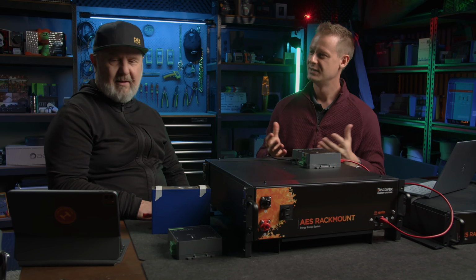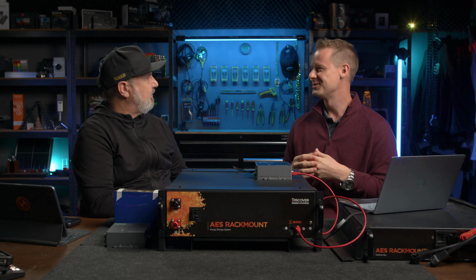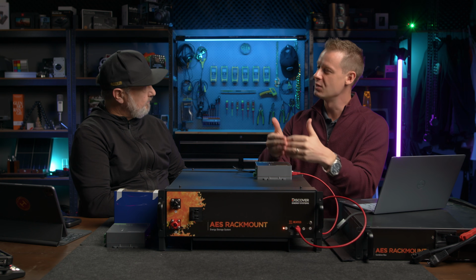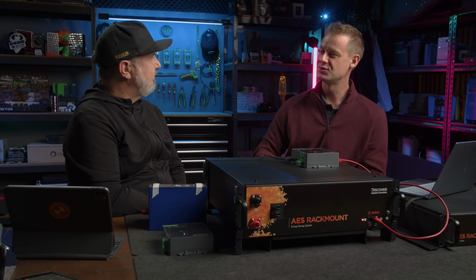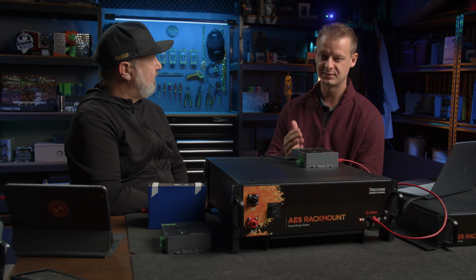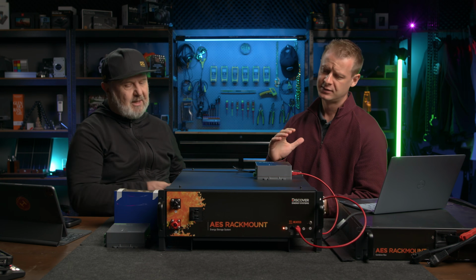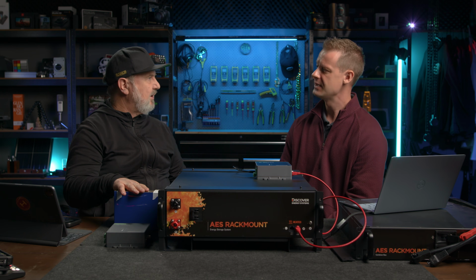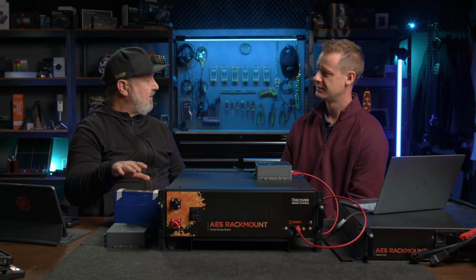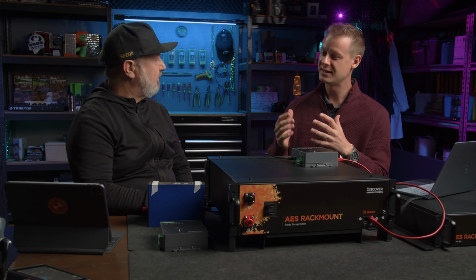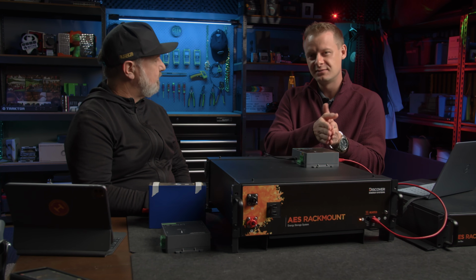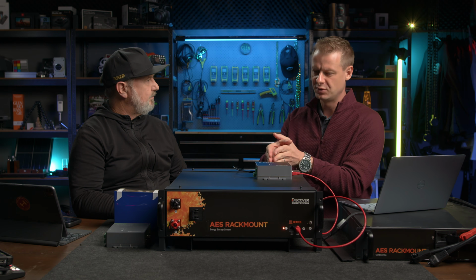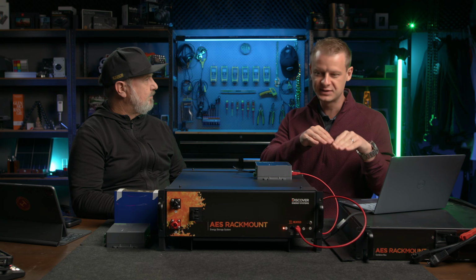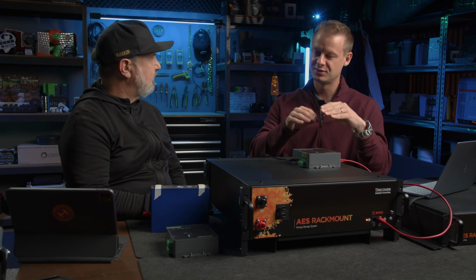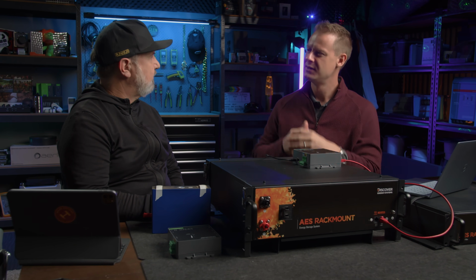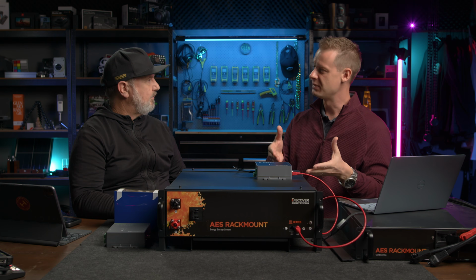If you use bulk and absorption terms, it allows you to stay in bulk longer. So that's how you get a faster charge with active dynamic charging. It's taking all the information like the cell temperature, the cell voltage, and balance - that's the key part. So when you exit your bulk phase and get into absorption, that's where you really see the active voltage requests start to bounce around, optimizing for internal balance.